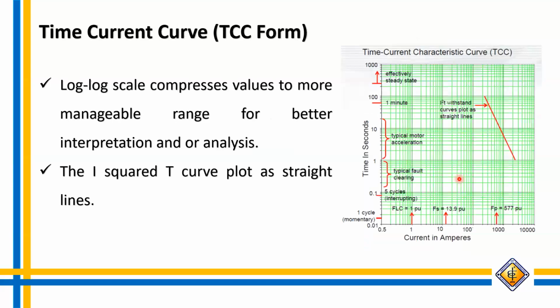So TCC, time current curve. A log-log scale compresses values to a more manageable range for better interpretation and analysis. Because a power system consists of high currents, since we calculate the fault current, it is 1,000 amperes. So we need a log-log scale to plot those critical points of current with regards to time. So the I squared T curve plots a straight line. So you can see here, on this side we have the time in seconds, and on the x-axis it is the current in amperes.